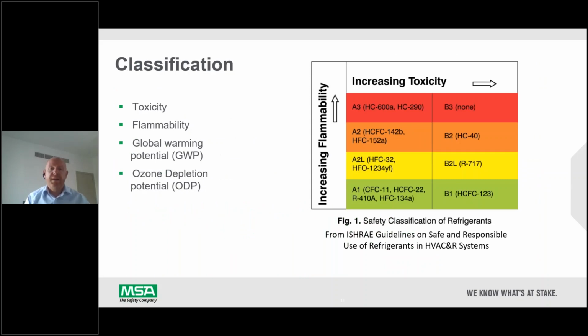So we classify refrigerants in terms of the flammability and the toxicity. This table actually forms part of the ISHRAE guidelines on safe and responsible use of refrigerants in HVAC and R systems. So you can see here for the flammability, it goes from 1 to 3, 3 being the most flammable. And then for the toxicity, you have A and B. Luckily enough, most of the gases which we deal with are still in the A1 category.